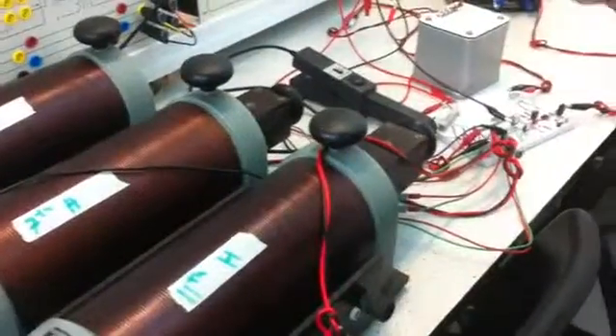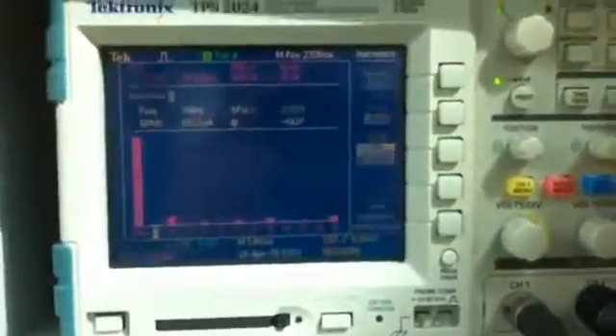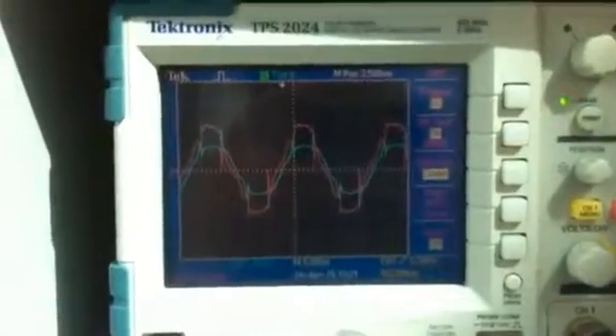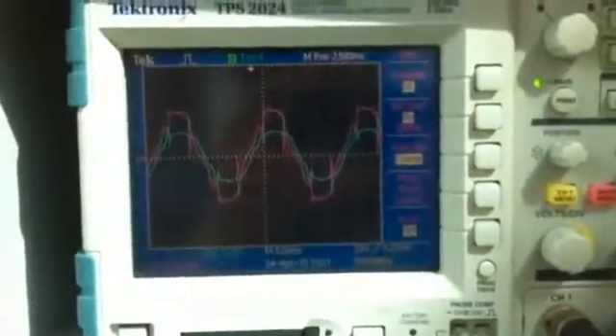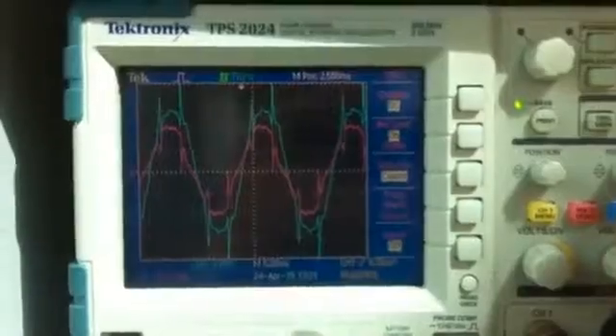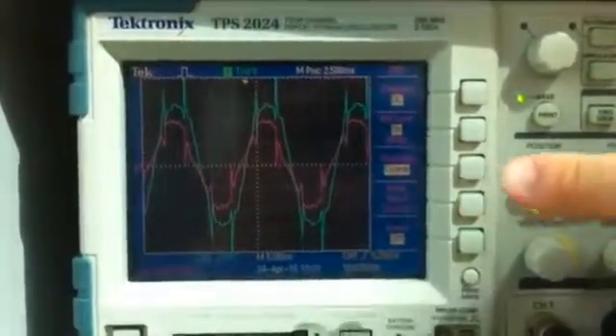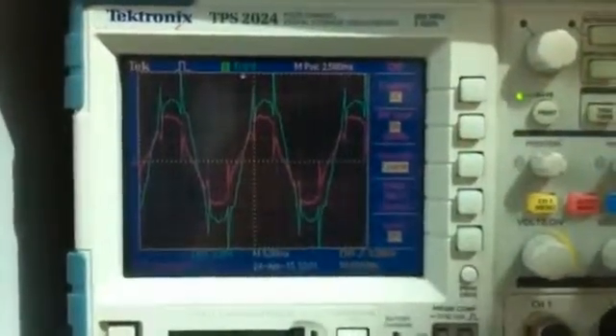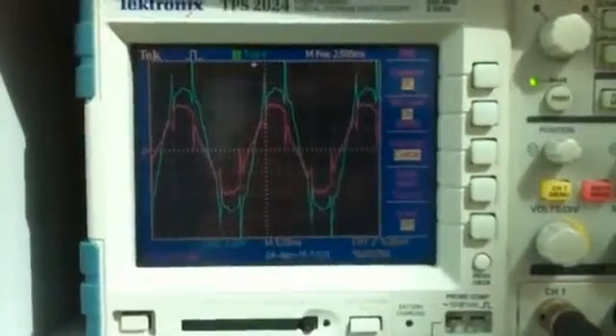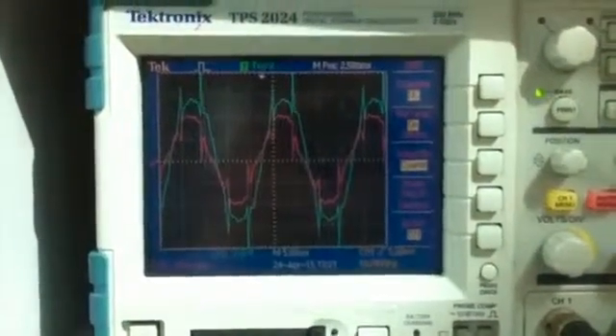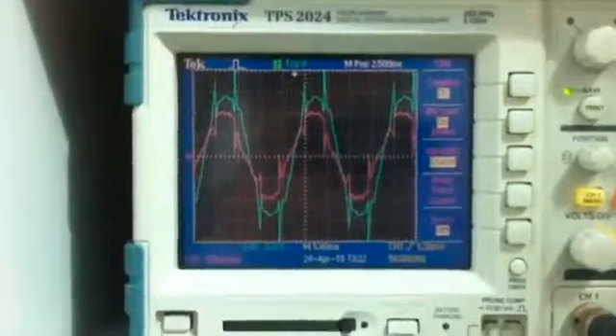All right, so that's the addition of all the filters, the 3rd, the 7th, and the 11th. And now to show you what the time domain current and voltage look like, this is it. As you can see, the current and the voltage are much more sinusoidal than they were before, which is the result of the reduction of the harmonics.